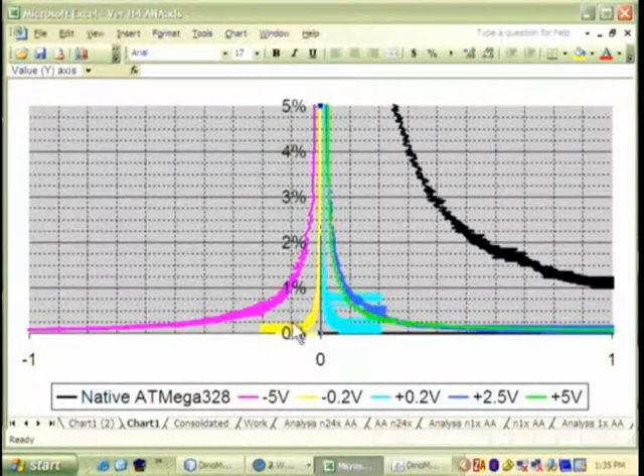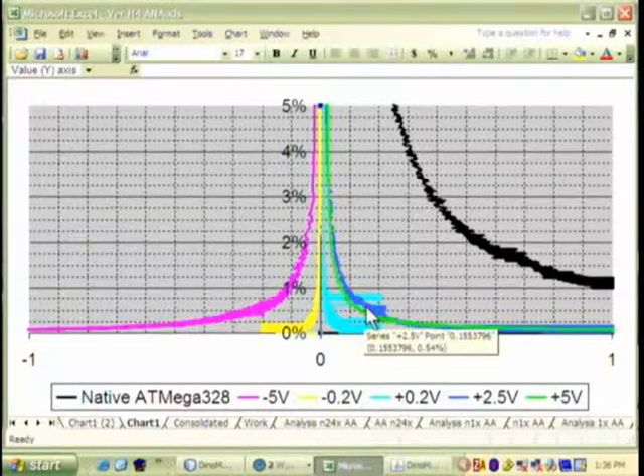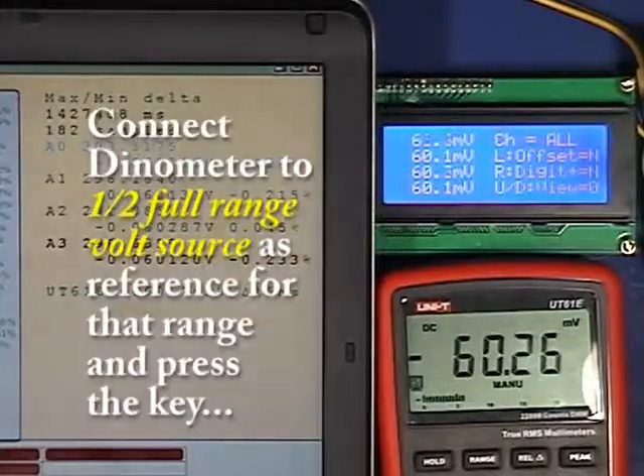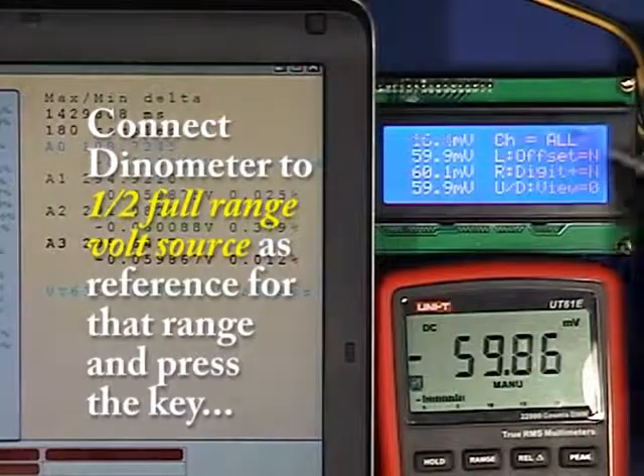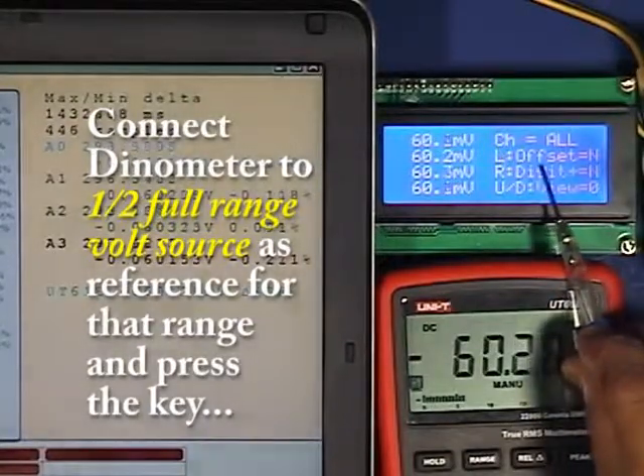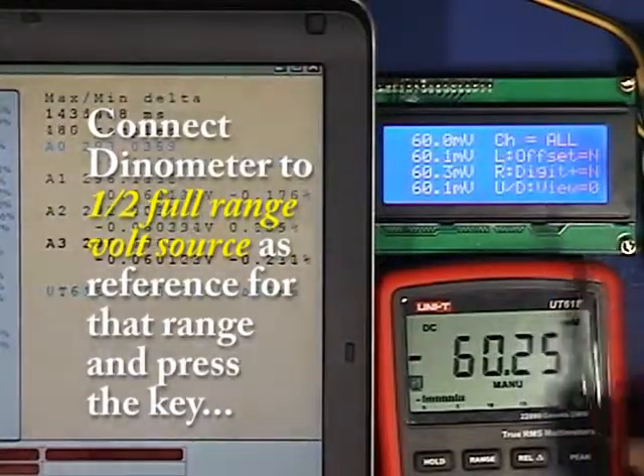On the other hand, the minus 200 millivolt is doing very good. The minus 5 volt, very good. The minus 200 millivolt, very good. And the plus 200 millivolt, very good, but certainly below 1% error. So the Dinometer, when the offset is properly adjusted, it does pretty good. Okay, now I'm selecting channel all. There's an option there for offset. When the offset is properly adjusted, it does pretty good.